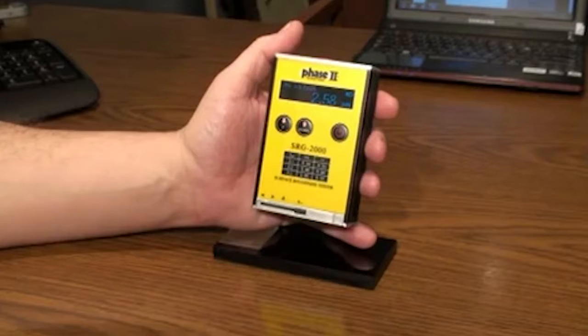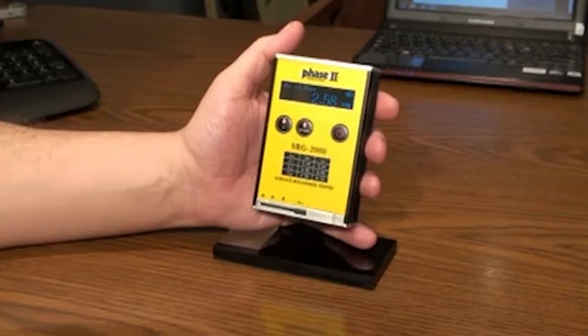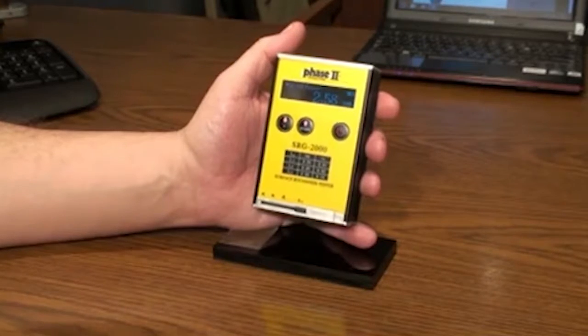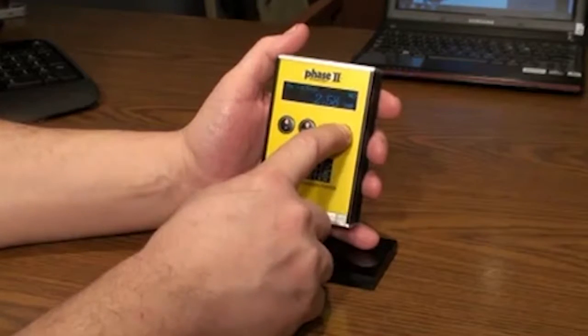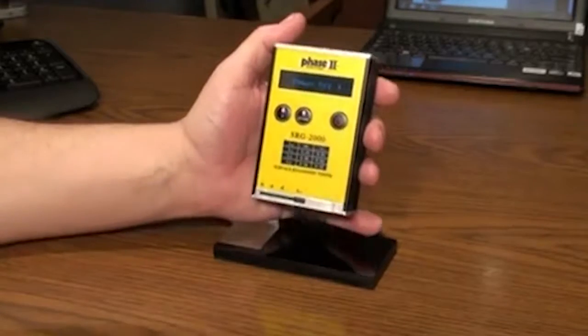Now that we're finished with the standard operation review, let's quickly go over the calibration mode. With the tester in metric mode and the power off, press the red start button on top while pressing the power button together.